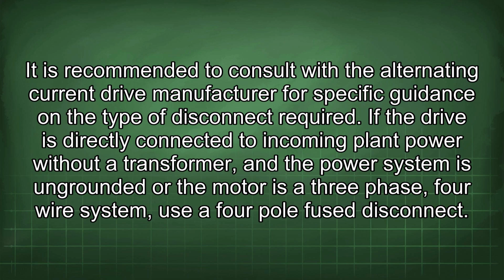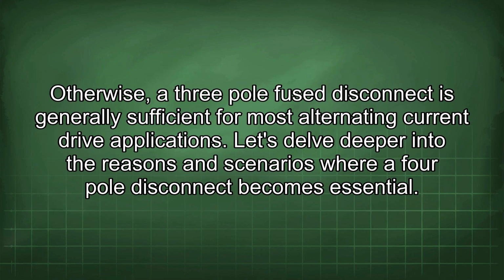If the drive is directly connected to incoming plant power without a transformer, and the power system is ungrounded or the motor is a 3-phase, 4-wire system, use a 4-pole fused disconnect. Otherwise, a 3-pole fused disconnect is generally sufficient for most alternating current drive applications. Let's delve deeper into the reasons and scenarios where a 4-pole disconnect becomes essential.